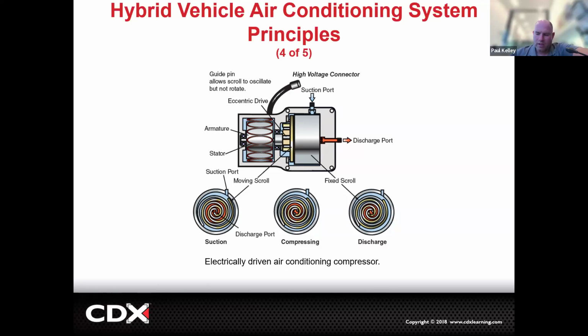So if that's three phase, cool. Now, if it's DC, there's just a positive and negative going to it, and it has its own inverter. Let's say this compressor is defective and not working. We'd need to make sure it's getting the DC right there, so if it's supposed to be getting 240 volts DC, you'd measure 240 volts.